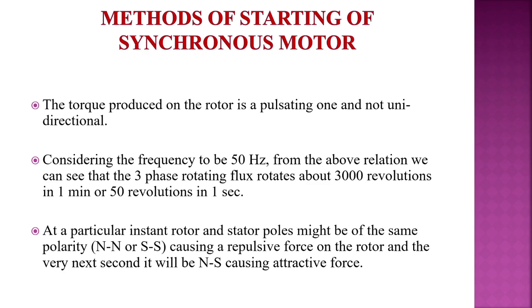Considering the frequency to be 50 Hz, from the above relation we can see that the three-phase rotating flux rotates about 3000 revolutions in 1 minute, or 50 revolutions in 1 second. At a particular instant, rotor and stator poles might be of the same polarity, that is north-north or south-south, causing a repulsive force on the rotor, and the very next moment it will be north-south, causing an attractive force.